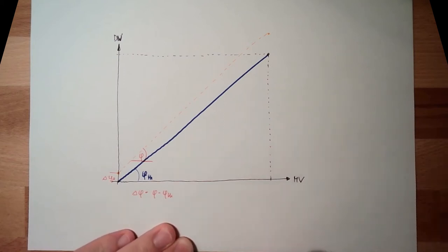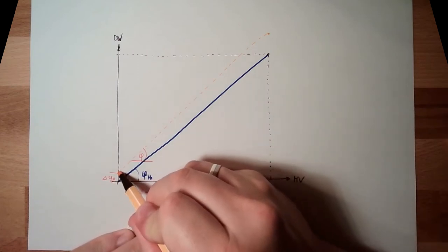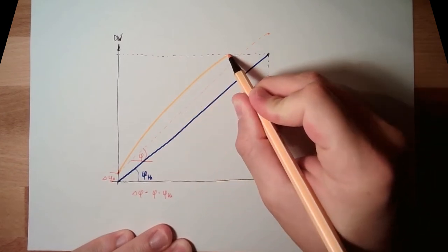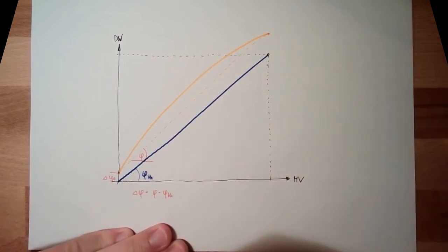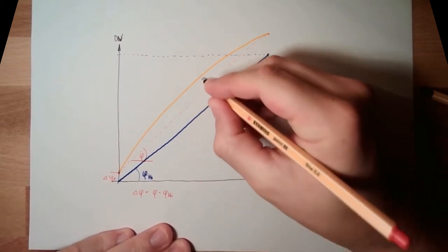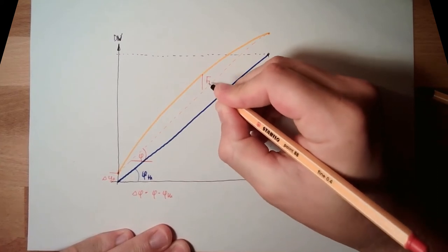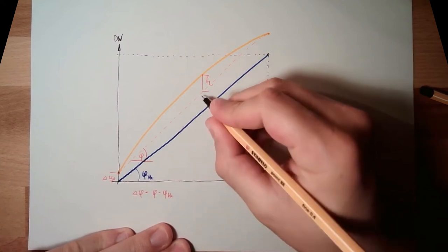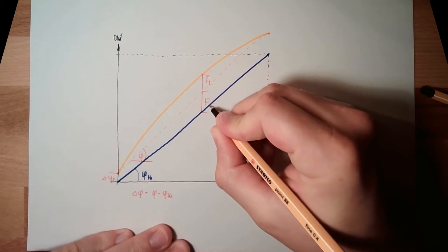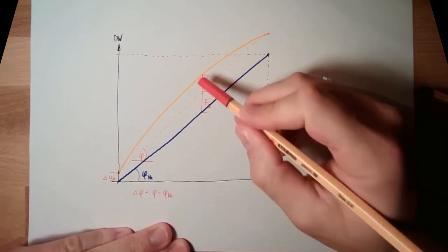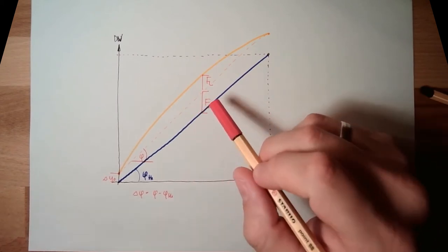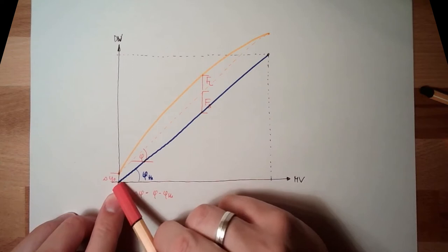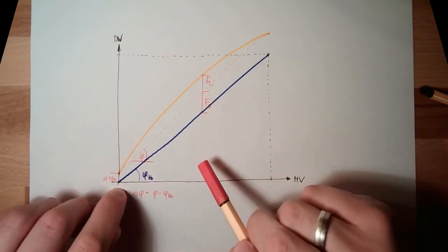Okay. Then there might be more. It might look like this, not linear, but curvy. Okay, so then we would have here a linearity fault. This is the measurement fault, or this is the line fault, let's call it, somehow a combination out of 0 point error and steep error, and then we have a linearity fault.